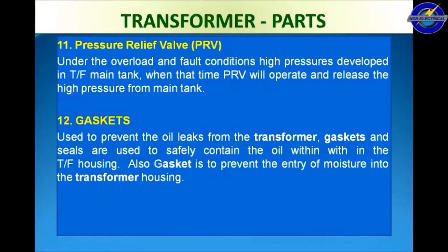11th one is the pressure relief valve. Under overload and fault conditions, high pressure develops in the transformer tank. At that time, the PRV will operate and release the high pressure from the main tank.